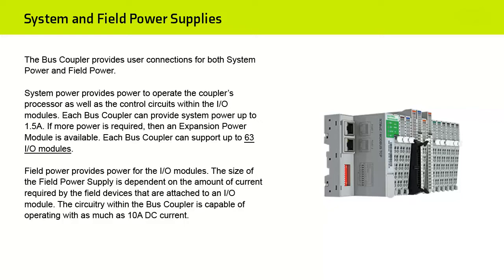Each Bus Coupler can provide system power up to 1.5 A. If more power is required, then an Expansion Power module is available. Each Bus Coupler can support up to 63 I/O modules.